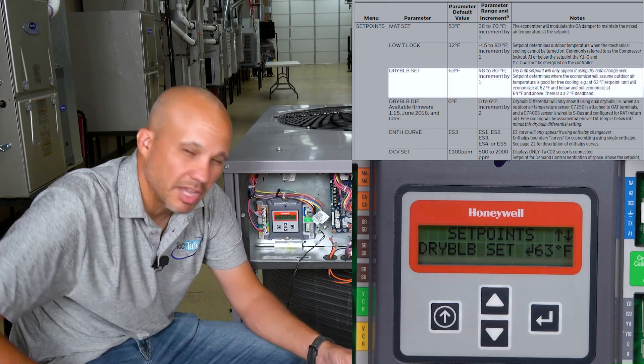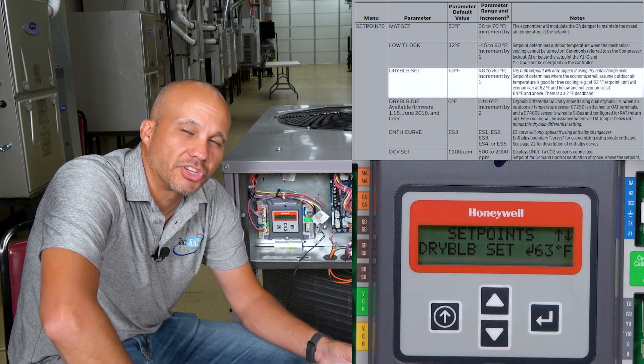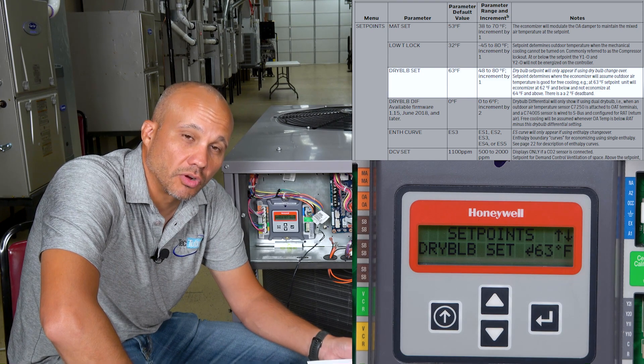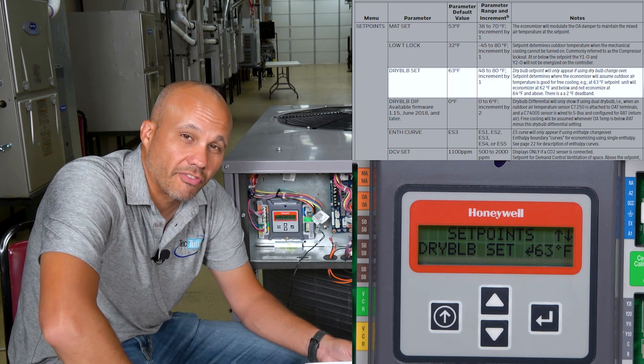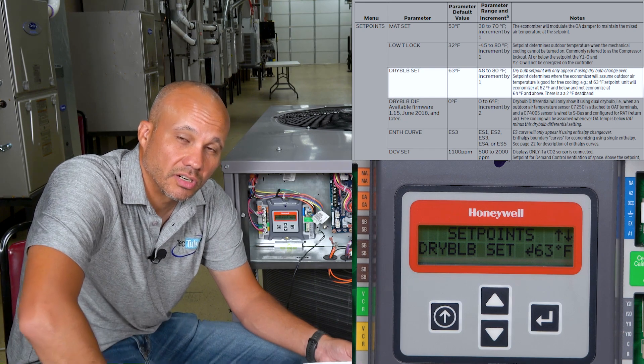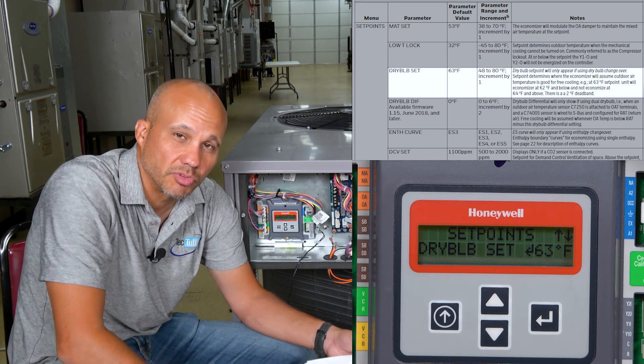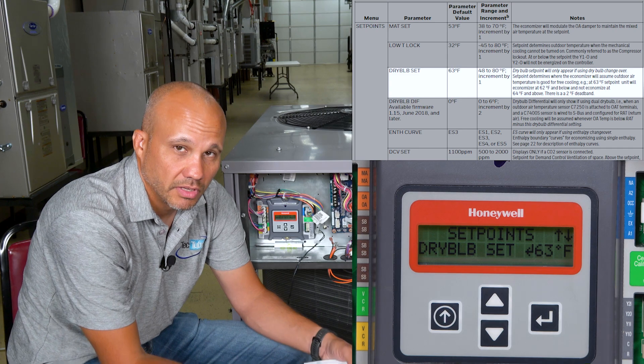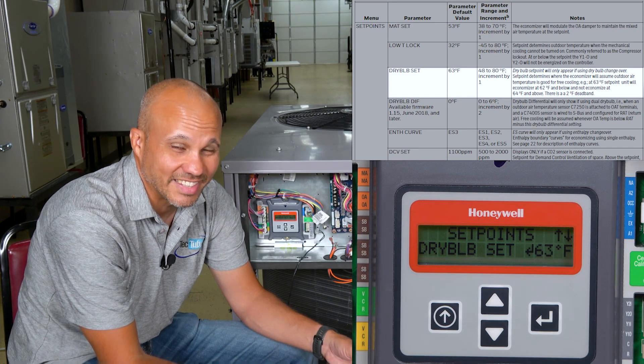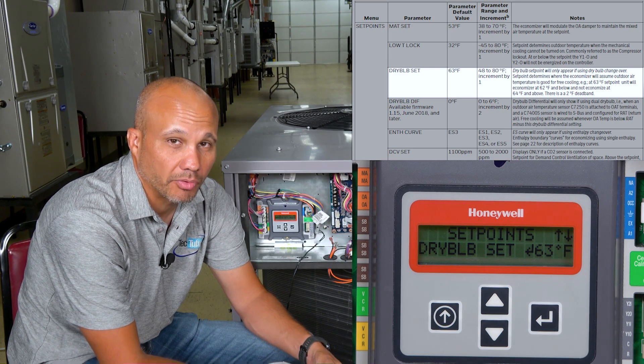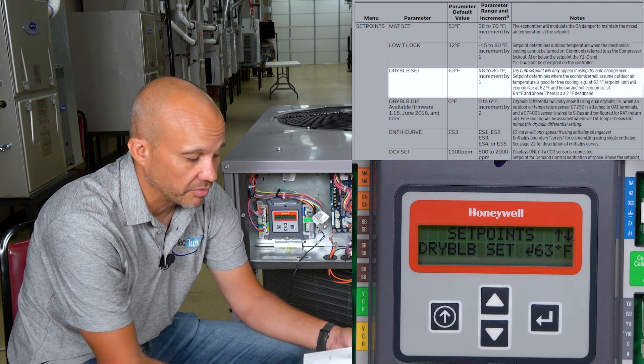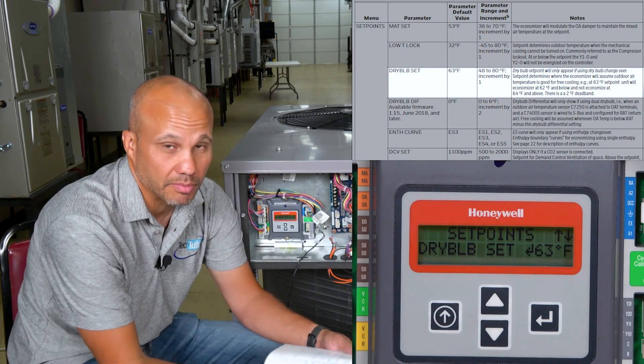Dry Bulb Set Point: the default is 63 degrees, which is a pretty good and most optimal setting. Most codes for most geographic regions will require a set point of 70 degrees, meaning if it's below 70 you have to use the economizer. I'm not a fan of having the economizer on all the time between 63 and 70 because there are some humid days where it becomes a problem. My suggestion: set it to 63, or comply with the code and upgrade to an enthalpy sensor instead of dry bulb.